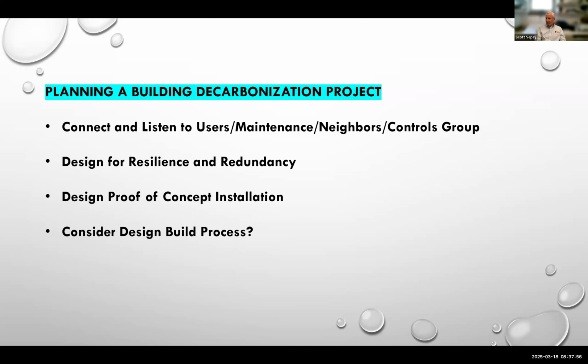You have to design for redundancy and resilience, designing for N+1 where you can on critical buildings, and study possible failure scenarios. Consider installing, for instance, 2 heat exchangers, maybe at 80% capacity rather than one at 100%. Consider 2 hot water pumps with at least 1 hot water distribution pump, and all freeze pumps, on standby power if you have it. So in a power failure, you can still heat the building's perimeter at least.